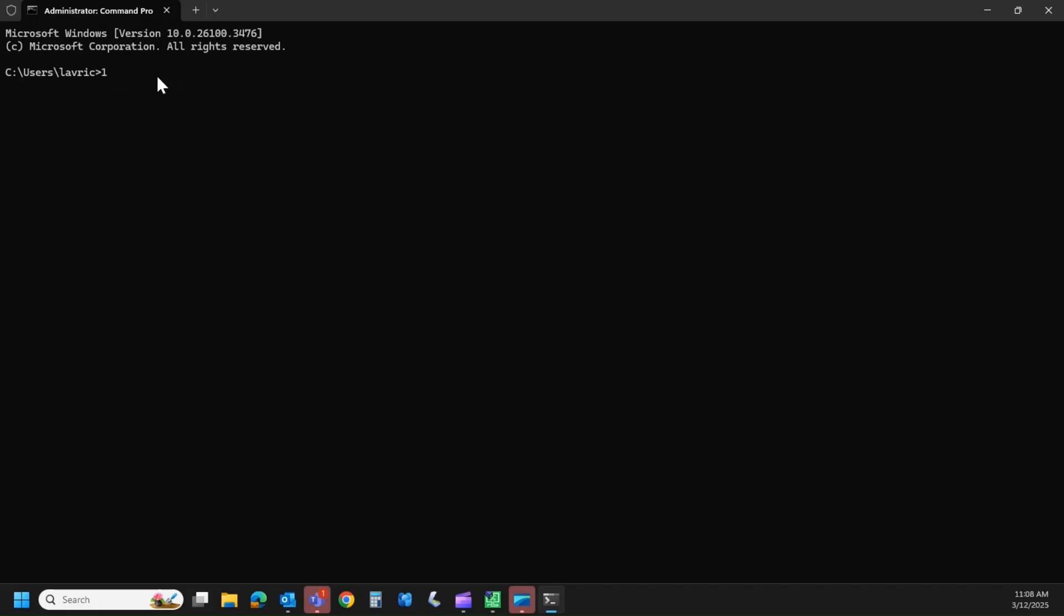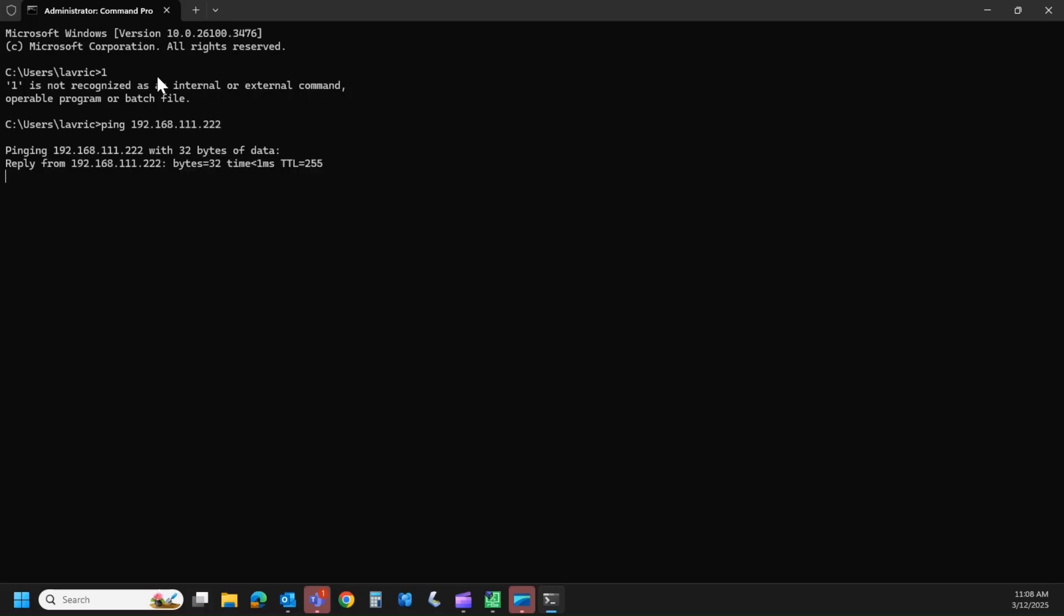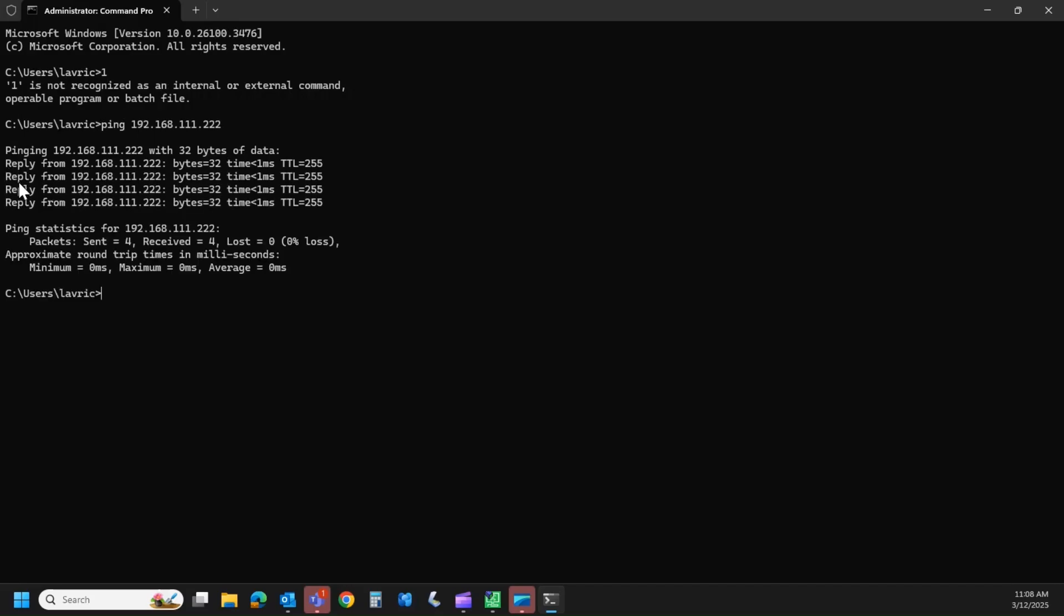So how I usually go here is to see if I've got that communication enabled, I type in ping, P-I-N-G, space, and then the address for the Mini 8, 192.168.111.222. When I hit enter, I should get a reply back from the Mini 8. If you don't get that reply back, it's likely because your PC has a different IP address than your Mini 8.